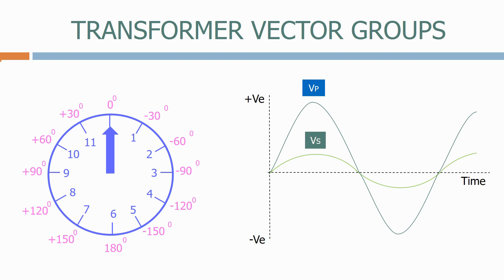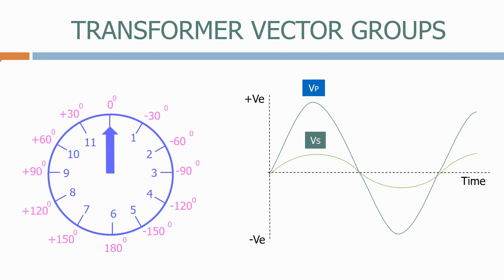Eleven o'clock will be plus 30 degrees. As we can see, the voltage on the secondary is now 30 degrees in advance of the voltage on the primary. Going the other way, one o'clock will be minus 30 degrees, which means that the voltage on the secondary winding is 30 degrees behind the voltage on the primary winding.